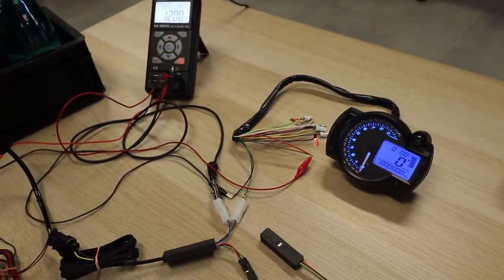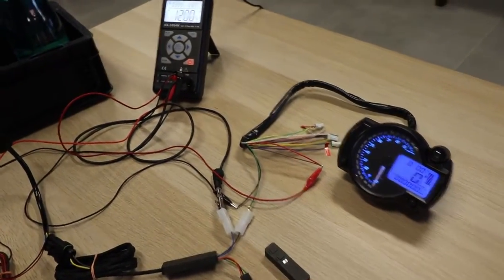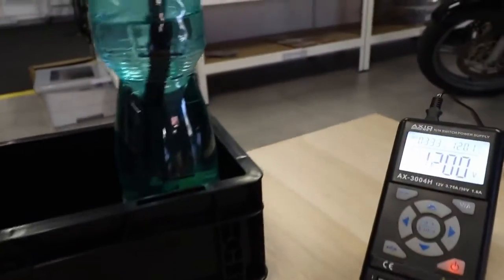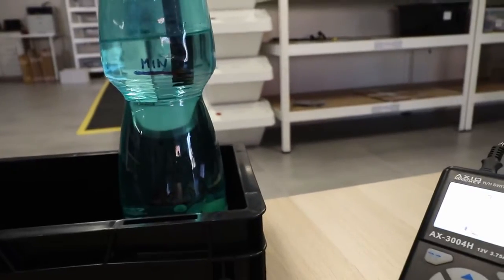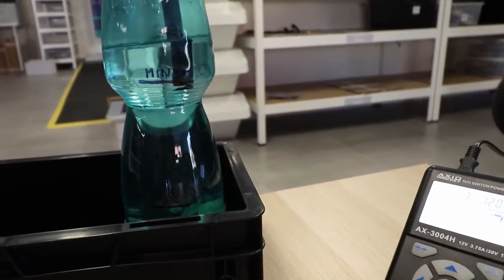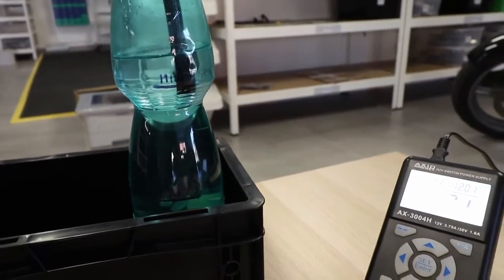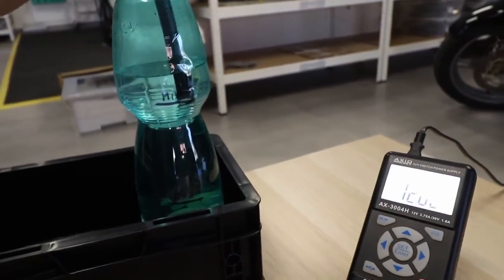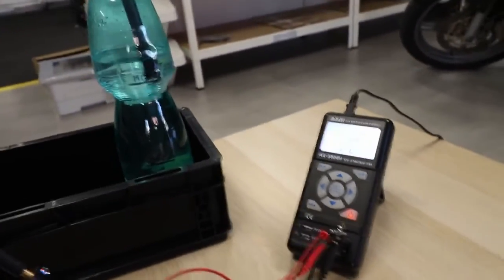Now let's calibrate the minimal level. The minimal level is when the minimal pressure is in the tube, so in this testing setup, it's when I put the tube at the upper side of the bottle. So I will put it there and hold the E button until the LED flashes one time.